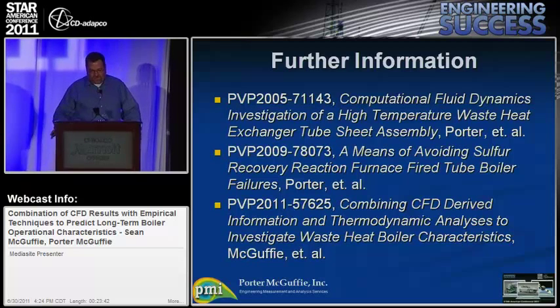No, for the thermal reactor, we don't include the combustion. What we assume is the inlet temperature. Obviously, with a large boiler like this, and especially getting into models that are 24 million cells just for the inlet side of it, we assume inlet flow rates that are evenly distributed, temperatures that are the firing temperature, usually measured from a piece of equipment called an E²T, which is an infrared temperature sensor.